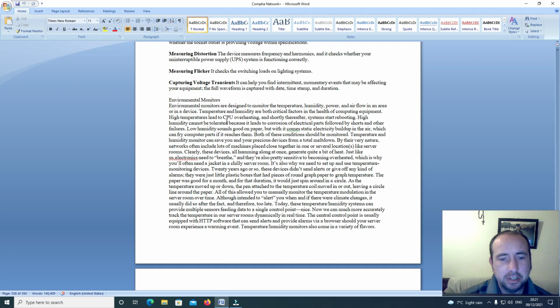High temperatures lead to CPU overheating, and shortly thereafter systems start rebooting. High humidity cannot be tolerated because it leads to corrosion of electrical parts, followed by shorts and other failures. Low humidity sounds good on paper, but it causes static electricity build up in the air, which can fry computer parts if it reaches them. Both of these conditions should be monitored. Temperature and humidity monitoring can save you and your precious devices from a total meltdown.